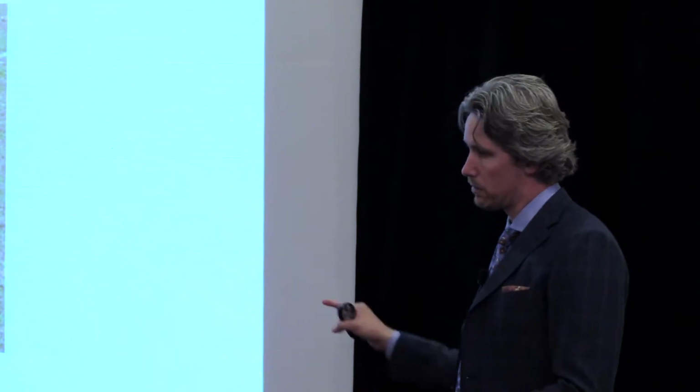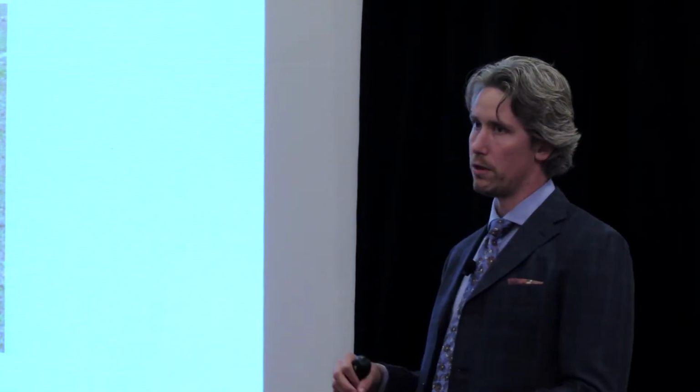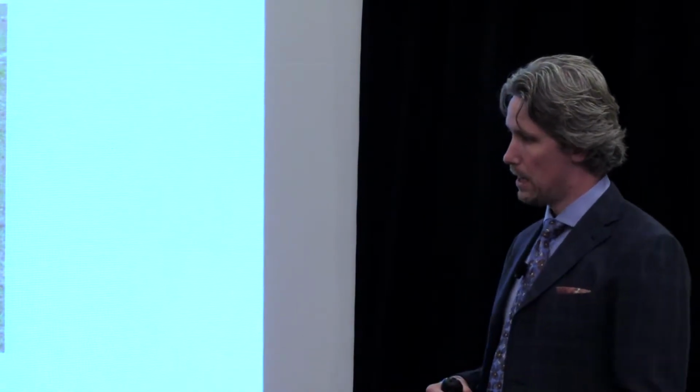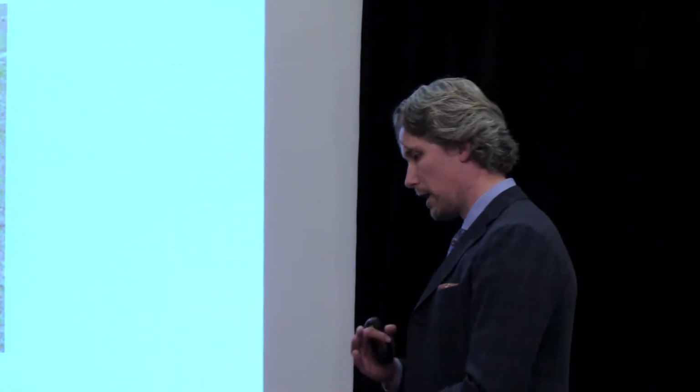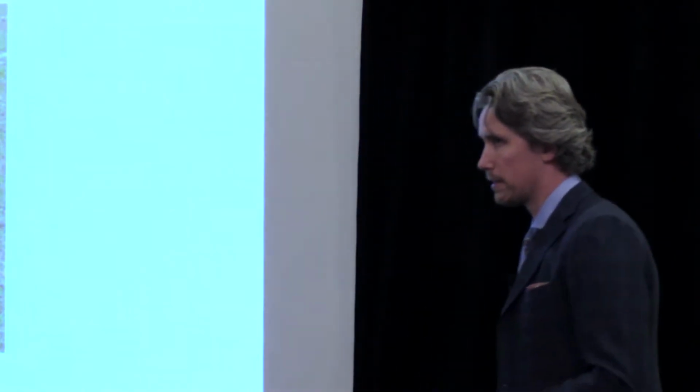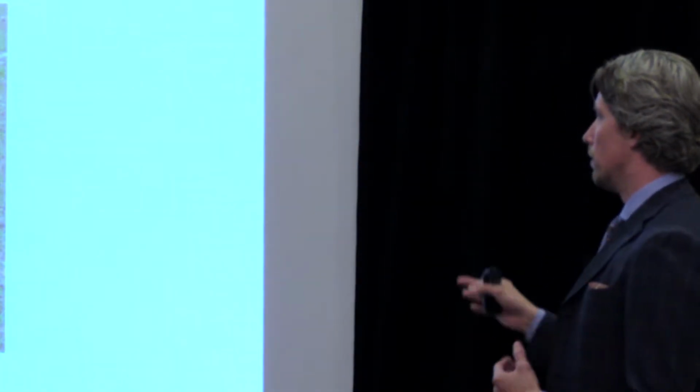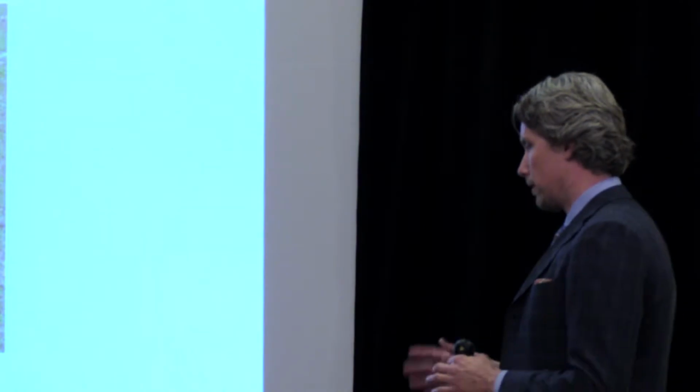But it's just absolutely not being willing to quit until your energy model's outputs match the historical data. A couple of the examples I'll go through are ones where there was an aha moment, and where we just could not get the energy model calibrated to the existing data. Then all of a sudden we realized something was going on, and then boom, the calibration happened as soon as we made that discovery.